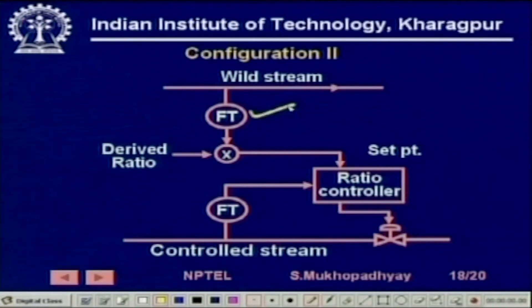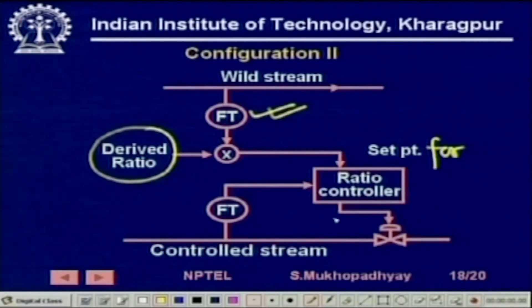There is another way by which you could do it. In this configuration, you are providing the set point from the wild stream. You measure the flow rate in the wild stream and multiply by the desired ratio to get how much of the controlled stream material should come. In that sense it is a set point for the flow rate of the controlled stream, and then it is a usual feedback control. You could do it in either manner and get the ratio.